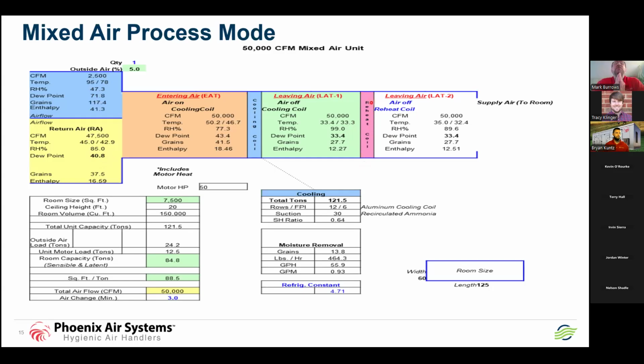If we just choose to put a reheat coil in this, we're going to heat the air from 33.4 dry bulb up to 35. It's very, very small. The point of this discussion is look what happens to the RH, the relative humidity. It goes from 99% down to 89.6. So we change the RH ever so slightly. You never ever with reheat change the dew point, and you certainly don't take any grains of moisture out. So then we'll evaluate this back to the compressor.